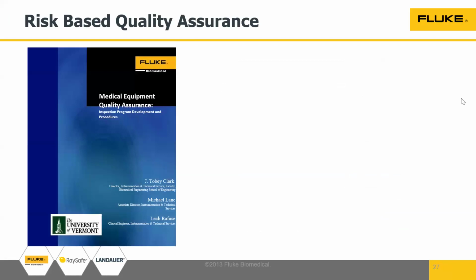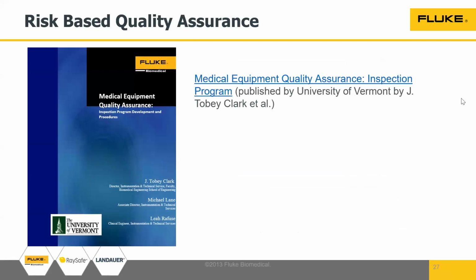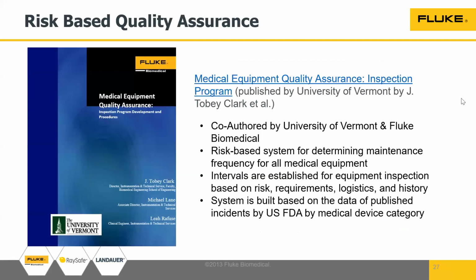We have this detailed risk-based study, co-authored by the University of Vermont along with Fluke, on risk-based determination of maintenance frequency for all medical devices. The intervals are established for the safety of the patient. This system is built on previous data available with the US FDA and various other medical device agencies.